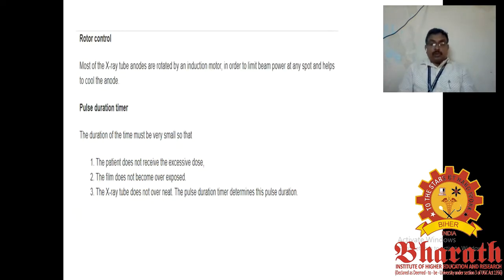The next is your rotor control, right. Most of the X-ray tube anodes are rotated by an induction motor in order to limit beam power at any spot and to help cool the anode, right. You see the entire process where more heat is involved, right. So, the movement of the X-ray head, the tube over the patient's body, you could have seen that with your practical experience also, you can realize this, right. So, it has to be done properly. So, that is why you need a rotor control, that is essential, right.